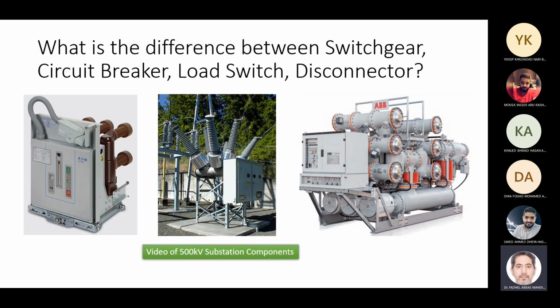But what makes a switch different is the capability, and we compare these elements by their capability to close or open. It's their ability to open or close a current. So what's the maximum current that these devices can switch on or break? In switches, generally, you can operate them to switch a load current, which is fine, up to full load current, either closing or opening. But they are not designed to break short circuits. So this is one important thing.